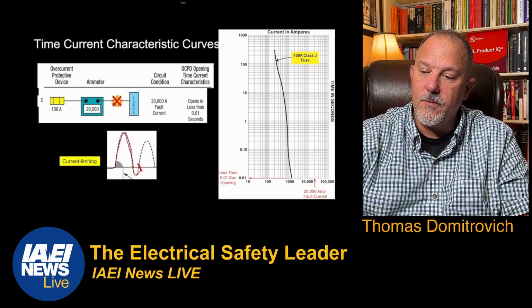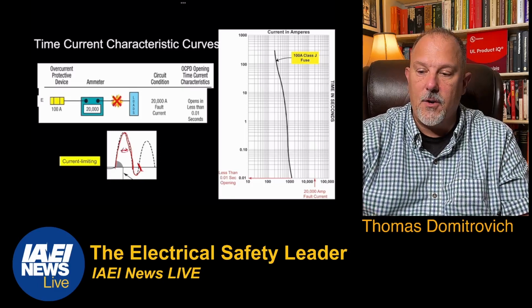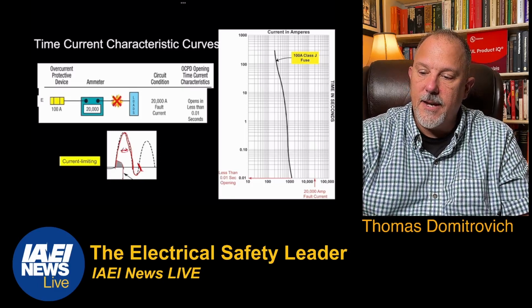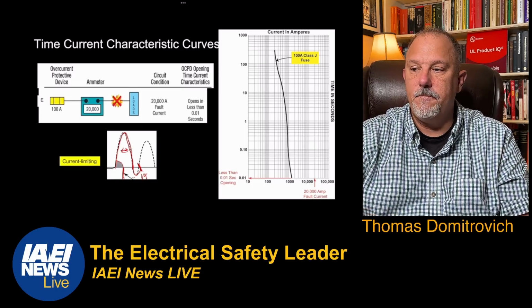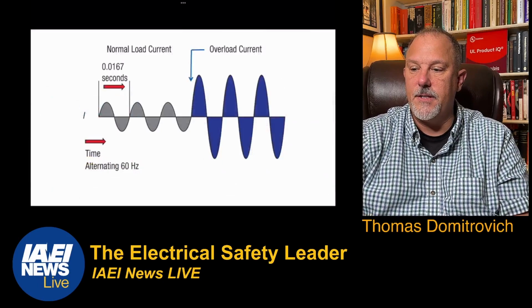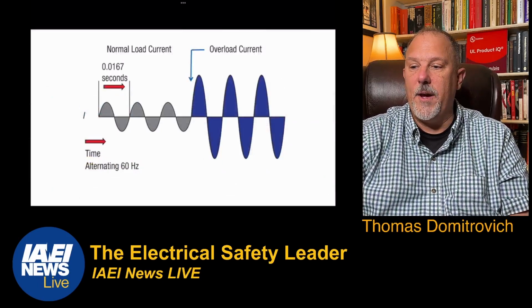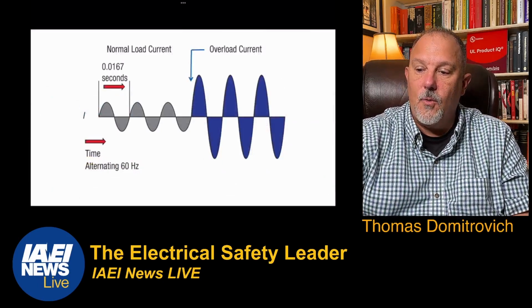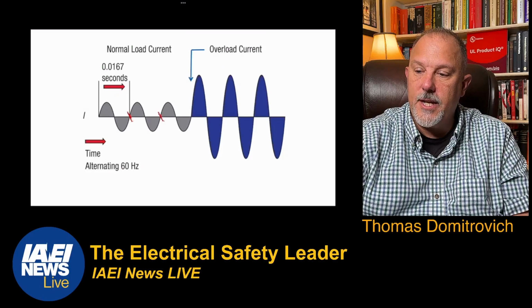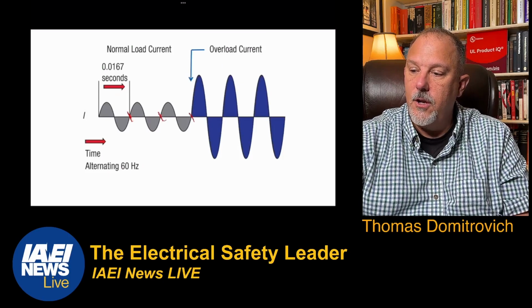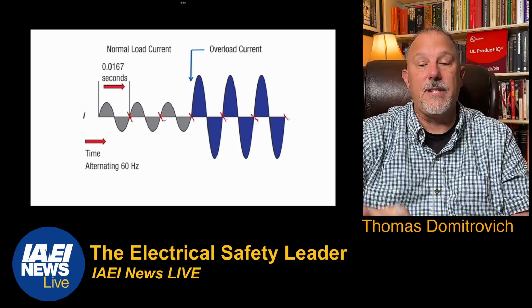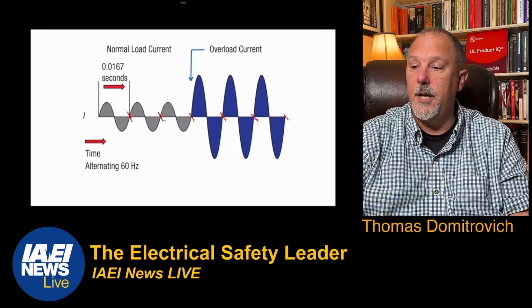This first right here, that first hump, that's a half cycle. And this clearing time right here is 1/4 of a cycle. That's a current limiting nature of a device. So what does that mean from a waveform perspective? So this is 1 cycle, 2 cycles, 3 cycles, 4 cycles, 5 cycles, 6 cycles.